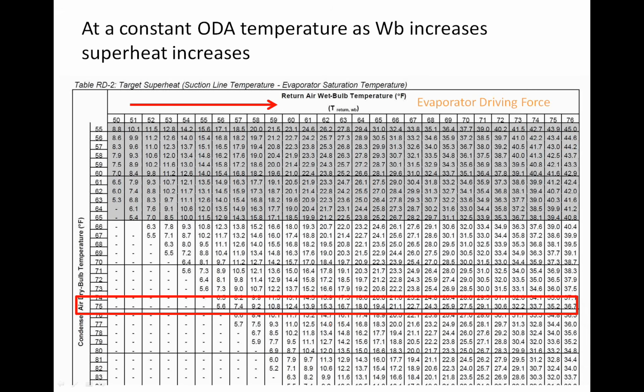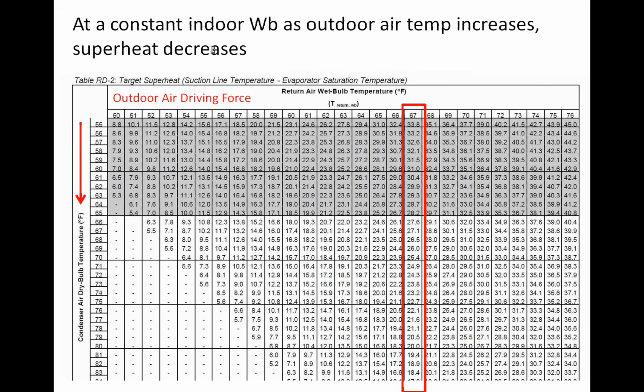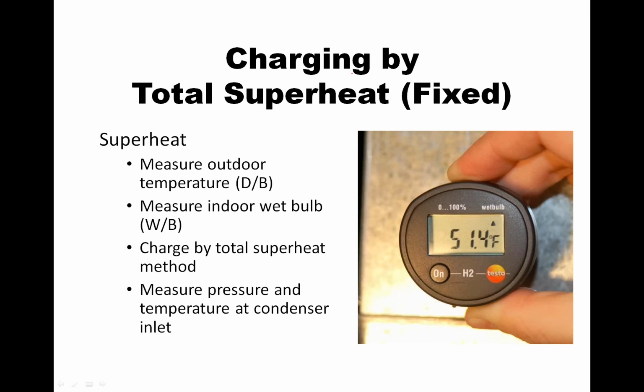So as you're charging a fixed orifice system, you have to periodically check your return air wet bulb temperature and make sure it hasn't changed, because if your wet bulb drops by a degree or two, your target superheat is going to drop also, and we'd have to readjust our target. If we go back a couple slides, you can see if we're charging by total superheat, we've got to measure the outdoor dry bulb, measure the indoor wet bulb, and charge by the total superheat method.